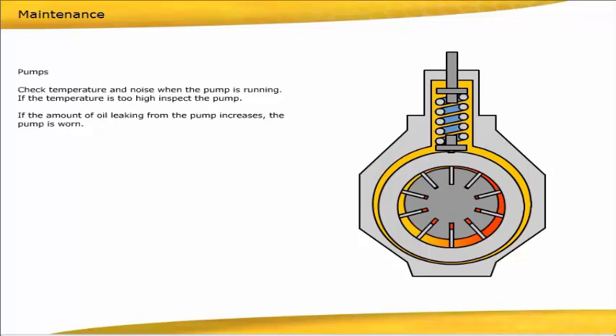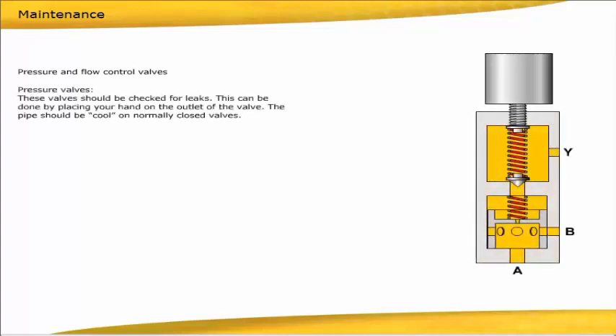Pressure and flow control valves. Pressure valves: These valves should be checked for leaks. This can be done by placing your hand on the outlet of the valve. The pipe should be cool on normally closed valves. Also check that the valve is correctly set and that the adjusting screw has not moved.